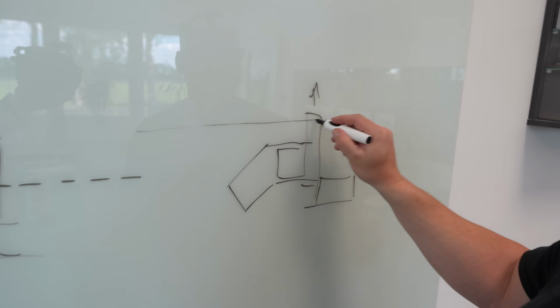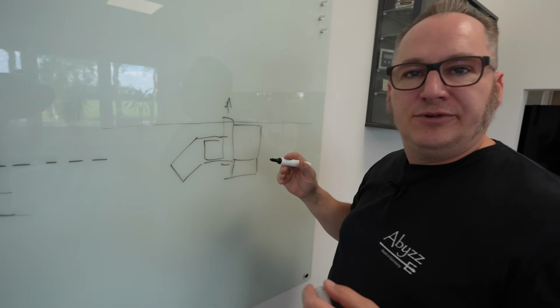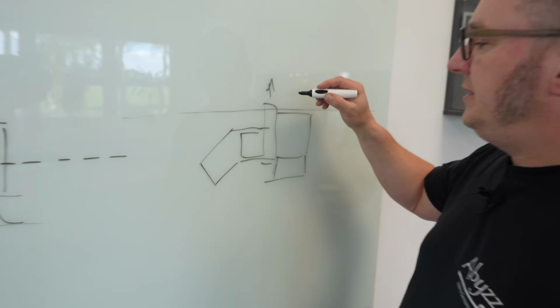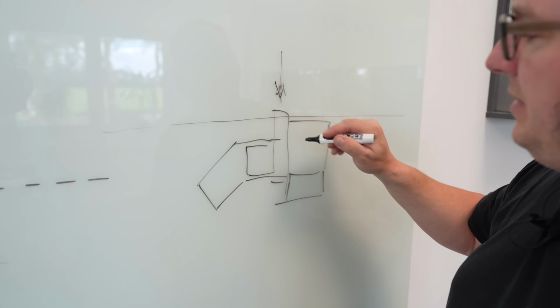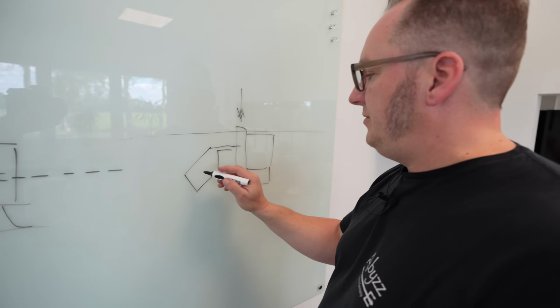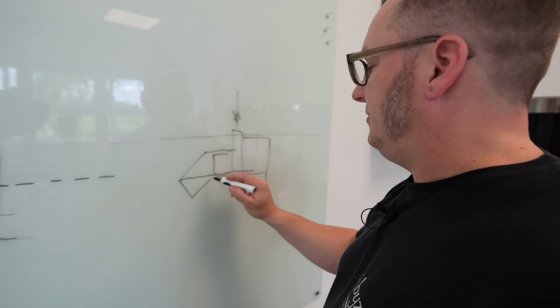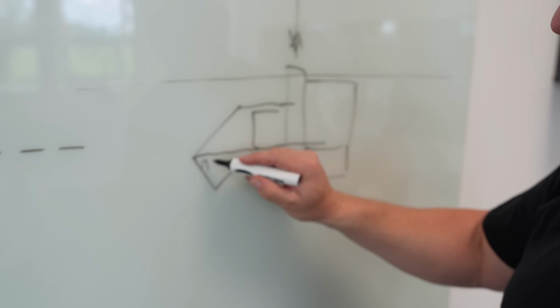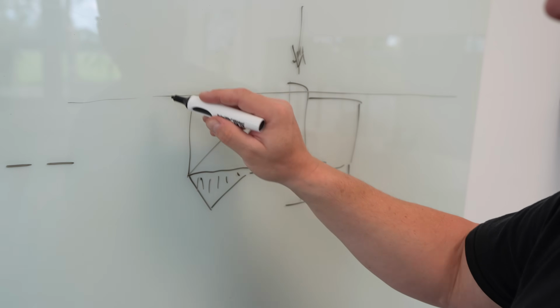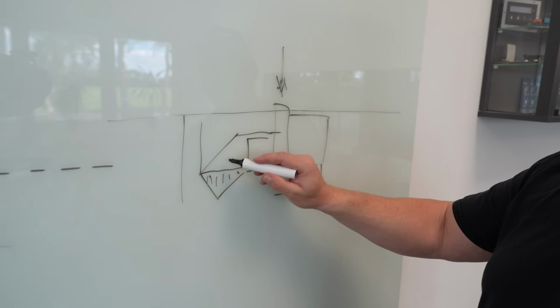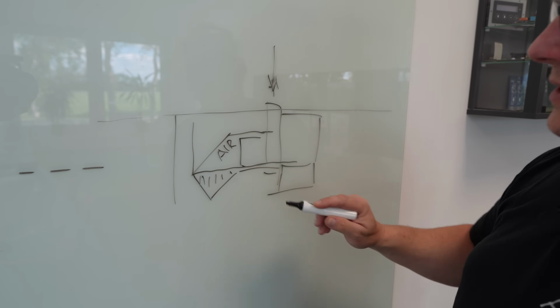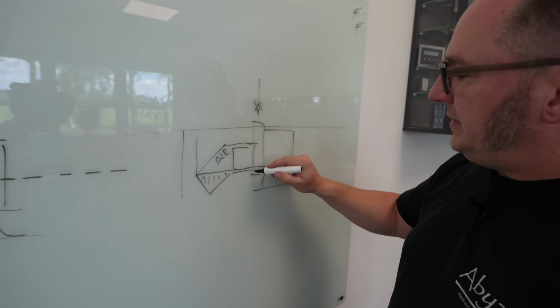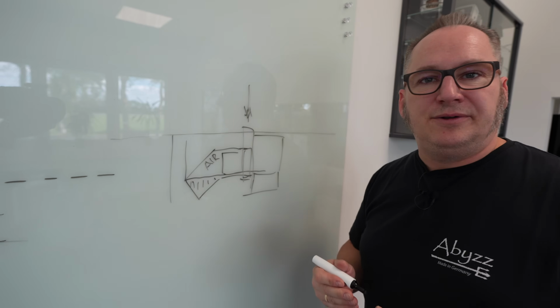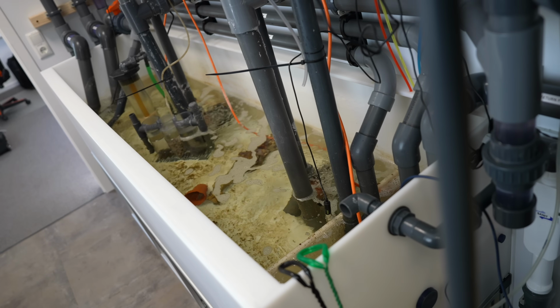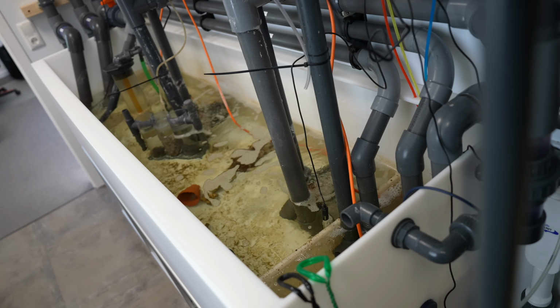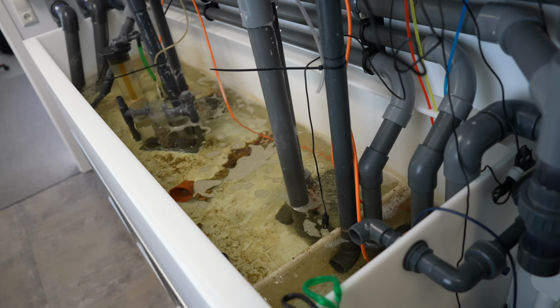Even if the water level is here, and now you switch off the pump for whatever reason, a feeding break or because you need to clean it, the water might rush back and drag air with it, basically creating an airlock in here. So this is water, and this is water, of course, so it's completely submerged, but this is all air. When you start up the pump, the impeller wheel is basically sitting only 1/3 in the water, and then the pump just can't start up. In my case, the pumps are using very little power. They're just running at roughly 55%. That's where it doesn't really matter.